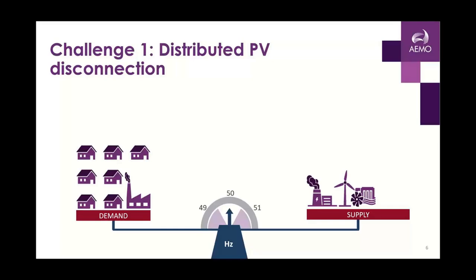Our role is really about balancing supply and demand continuously and instantaneously. This is measured through frequency, which you see here. We do have a buffer within which we can manage the supply and demand, and we have to manage that seesaw. But if it goes outside of those buffers, there is potential for damage to equipment or appliances. So we incorporate a number of mechanisms to try to maintain that, such as under frequency load shedding, which I'll talk about later. And if we can't manage it within this buffer zone and it is really problematic, we could end up in a full blackout and a quite severe event if our supply and demand isn't well balanced.